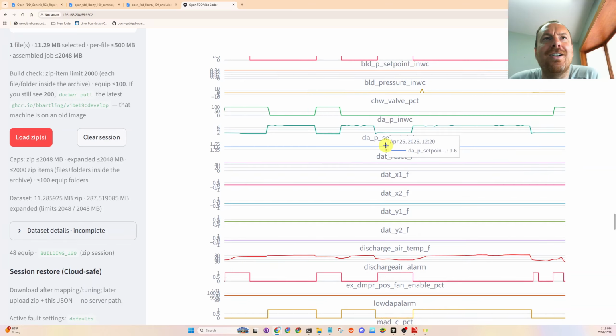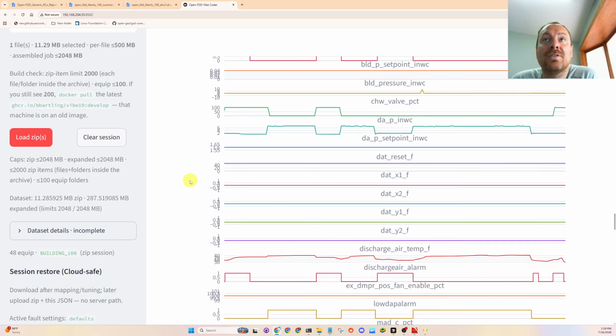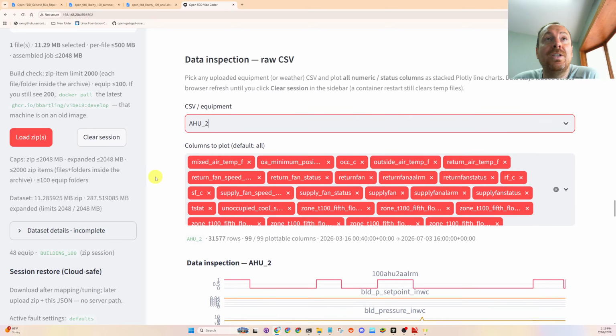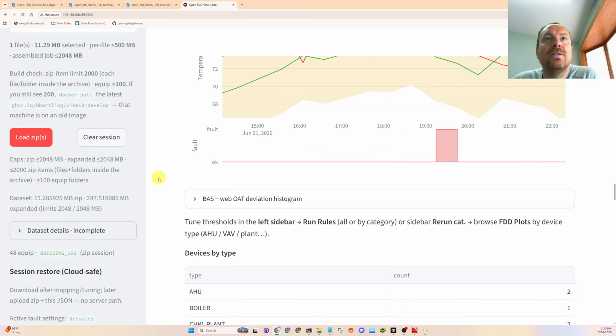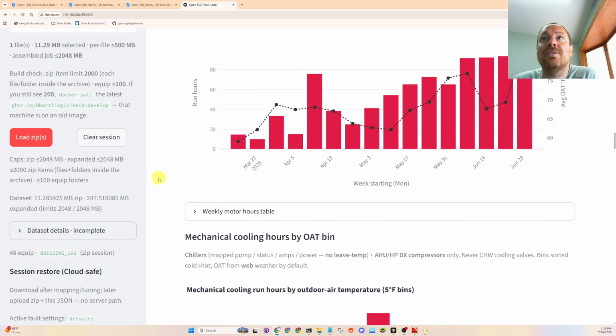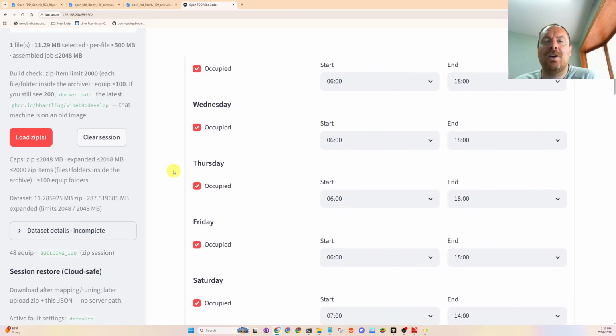Okay, so the DAP underscore inch water column, INWC. Something is going really wrong here, where I notified the client that there is something really off. So this 7 inches water column is a ton of static pressure, where usually the duct systems might not be rated for much more, where you could be really stressing the ductwork. So that's something I also see really odd.